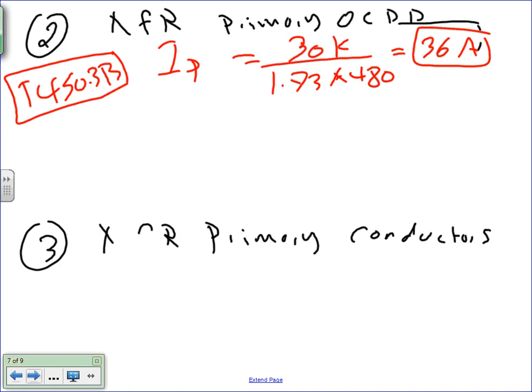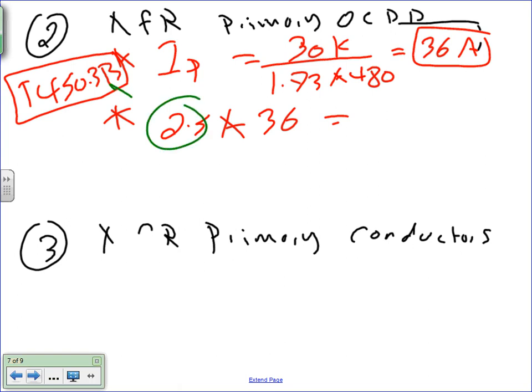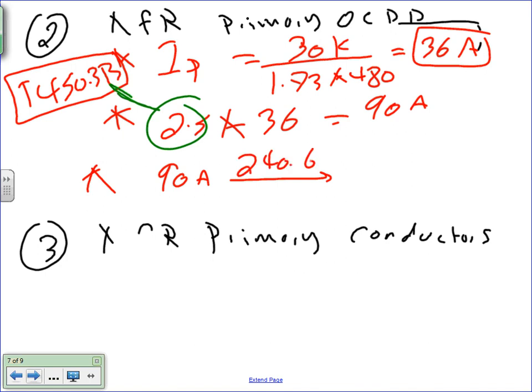If you go to 450.3(B), it tells you you can multiply it by 2.5. So step number one, step number two, 2.5 times 36. Where did the 2.5 come from? From 450.3(B), right? Everybody can see that multiplier coming right from here. You do your math on this, and that gets you 90 amps. And then the last thing you need to do is take the 90 amps to 240.6. If it's not a standard size, what do you need to do? You need to go to the next standard down. We happen to have a standard size, so we don't need to worry about that one. 90 amps. If it was 94, you can't go up, you have to go down. 90.